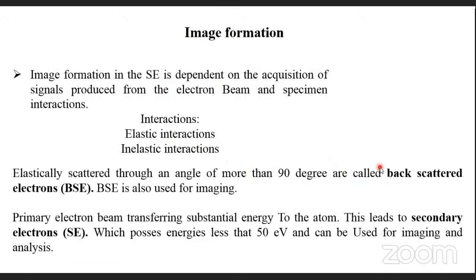How an image is formed: electrons bombard the sample and we get secondary electrons, backscatter electrons, Auger electrons, X-rays, etc. These secondary outputs are taken by detectors. Secondary electrons are formed by inelastic interaction. Backscatter electrons are just like rubber balls — when you throw a rubber ball on a floor, it bounces back. The electrons fall on the sample, bounce back, and are detected by the backscatter electron detector, giving us beautiful contrast imaging for nanocomposite samples.